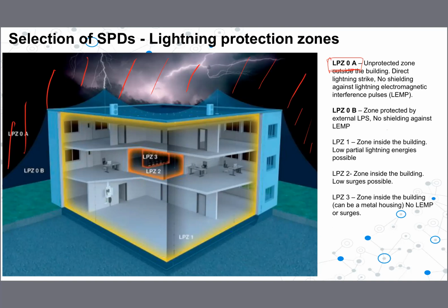We have a lightning protection system for this particular building, but the shaded area in red color is not protected by the lightning protection system provided. So there can be direct lightning and also no shield, no protection against lightning electromagnetic interference, LEMP. If there is a direct lightning, it can hit whatever equipment or structure is in this area. And also if there is a lightning strike nearby, there can be induced voltages because there is no shield against lightning electromagnetic interference.